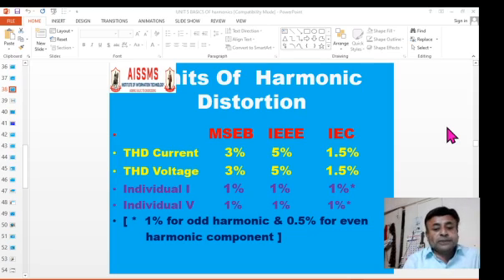Similarly, for voltage also it is 1%. IEC has stated 1% for odd harmonics and 0.5% for even harmonics. Because even harmonics are very less, we have seen that because of a symmetrical waveform, the even harmonic shapes cancel each other and therefore the resultant is 0.